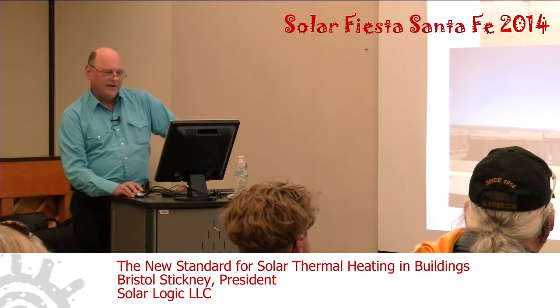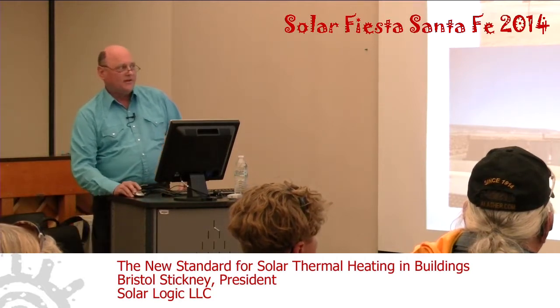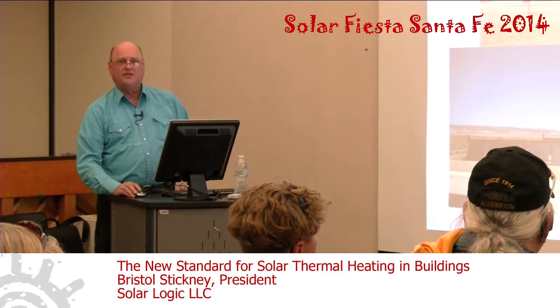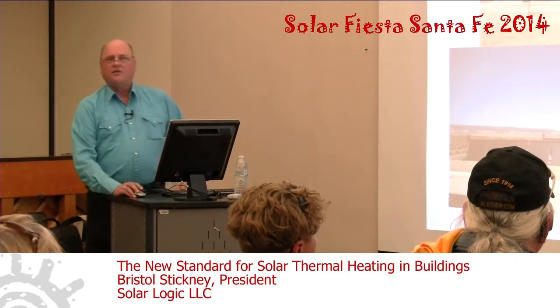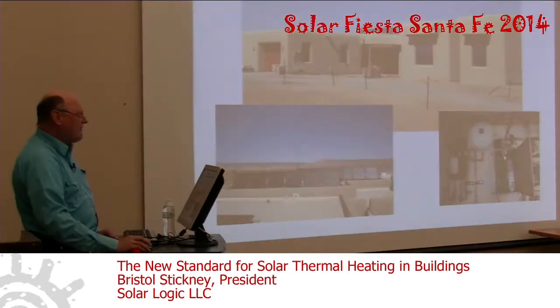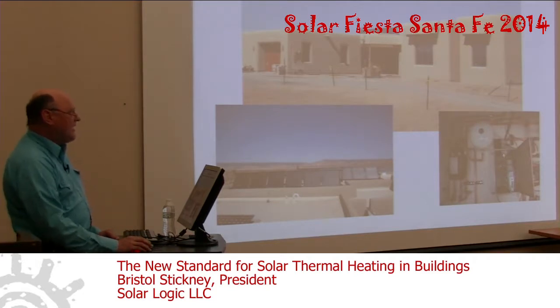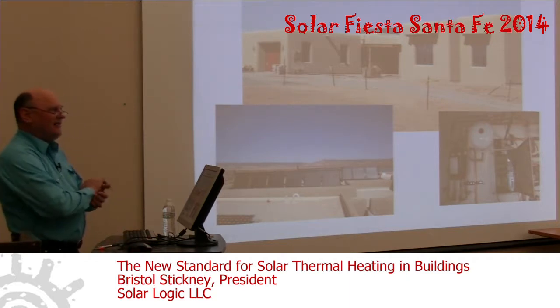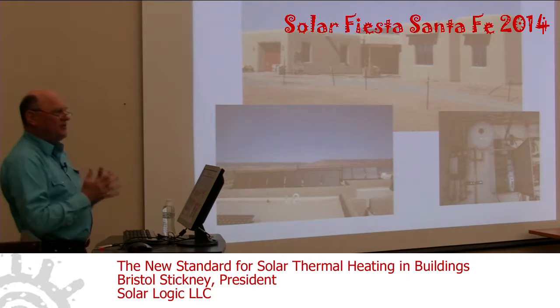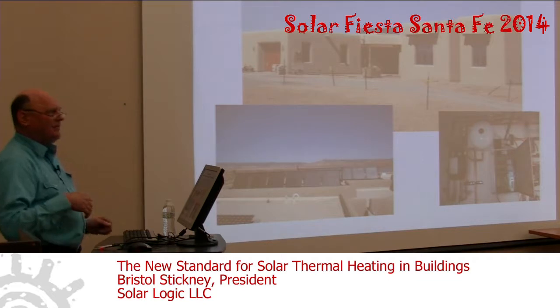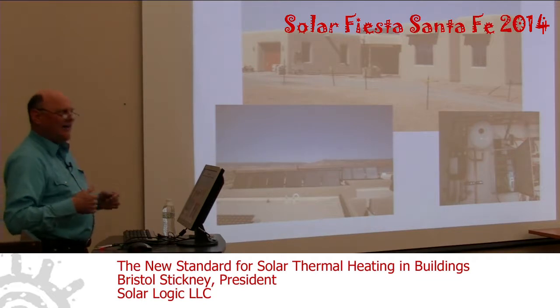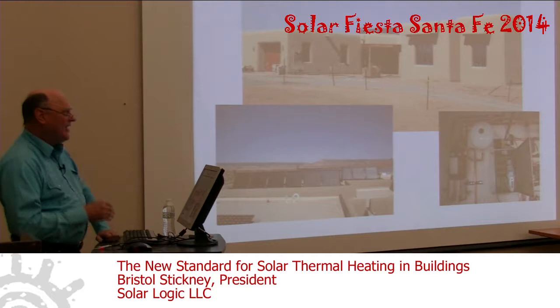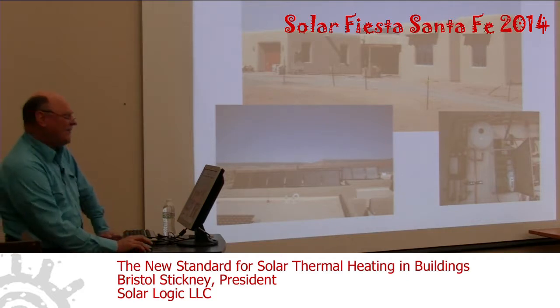So what you can see here is the control system that controls the entire heating system in the house: the solar, the propane, the water heater, the warm floors, the room thermostats. Everything goes through this box, and this box has a computer in it right there, and that is the secret of controlling the new standard. We use software in a computer to control this. So it's no longer done with relays and hand wiring. It's all computer software, and it's all internet compatible.